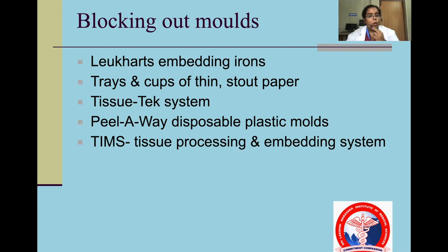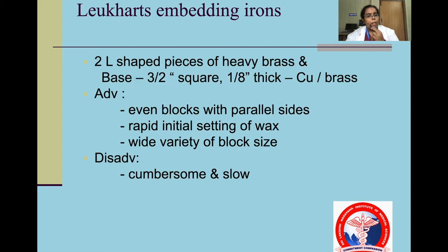Blocking out molds are metal or plastic molds that help to get the shape of the paraffin block. These include Leuckart's embedding iron, trays and cups of thin stout paper, Tissue-Tek system, Peel-A-Way system, and tissue processing and embedding system. Leuckart's embedding iron consists of two L-shaped blocks of heavy brass used to level the blocks with parallel sides, giving rapid initial setting of wax and a wide variety of block sizes, though it is cumbersome and slow.